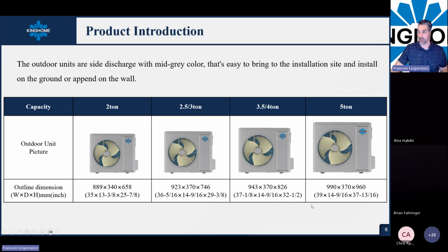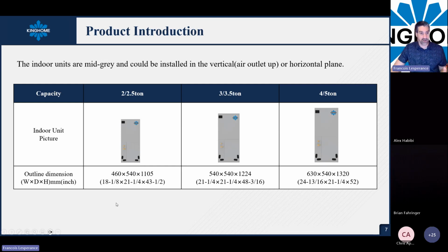Between the 2 ton and the 5 ton, you'll see about 4 inches difference in width and maybe 3 inches difference in depth. You need to pay attention to that. It's more plug and play with the economic model. You don't have to manage all the dip switches and all the rest, because we're using a different cabinet for each capacity. Same thing for the air handler: we have a different cabinet to match each capacity. So we will go with the same thing right here.